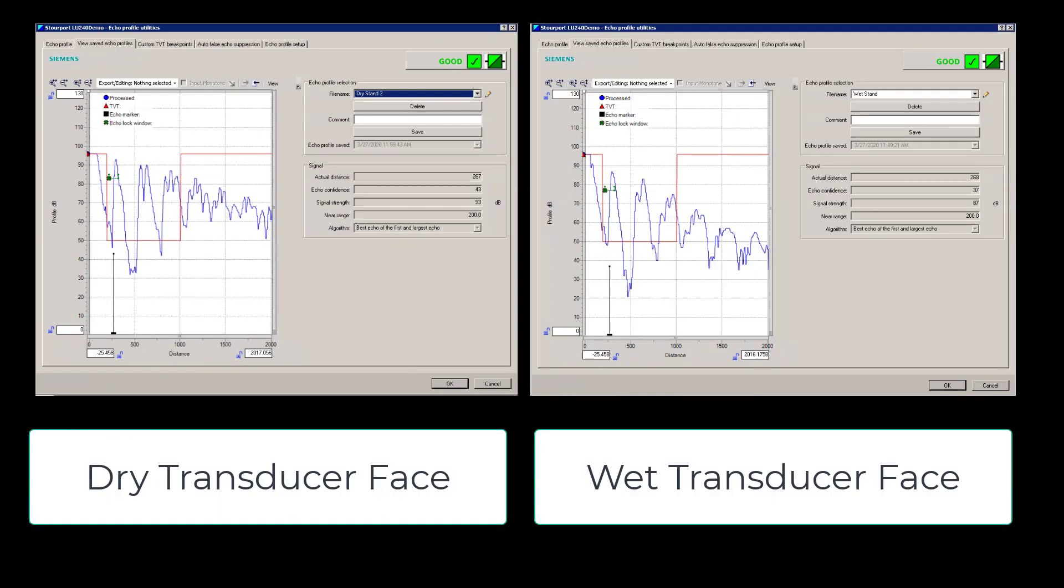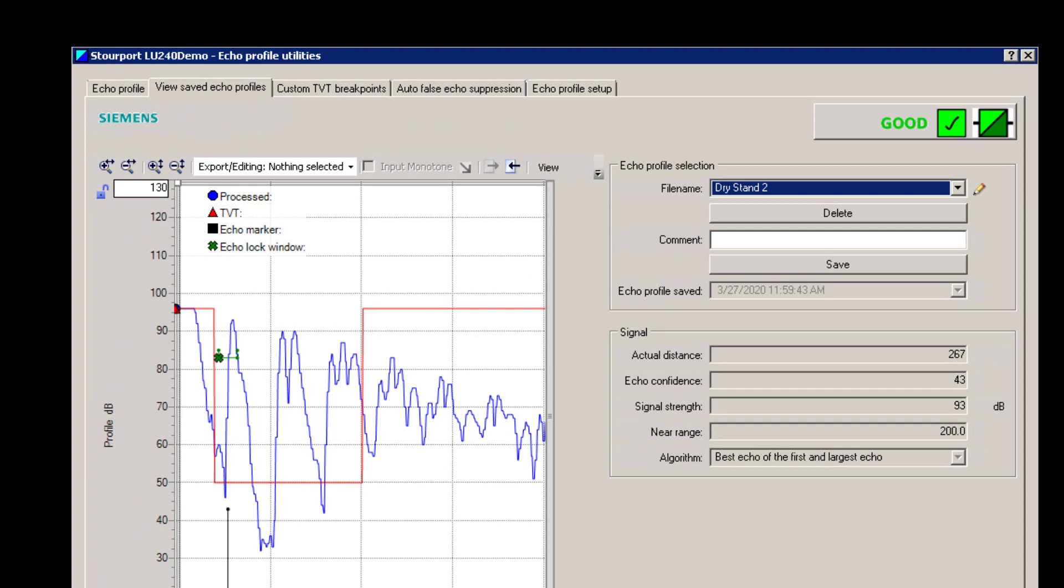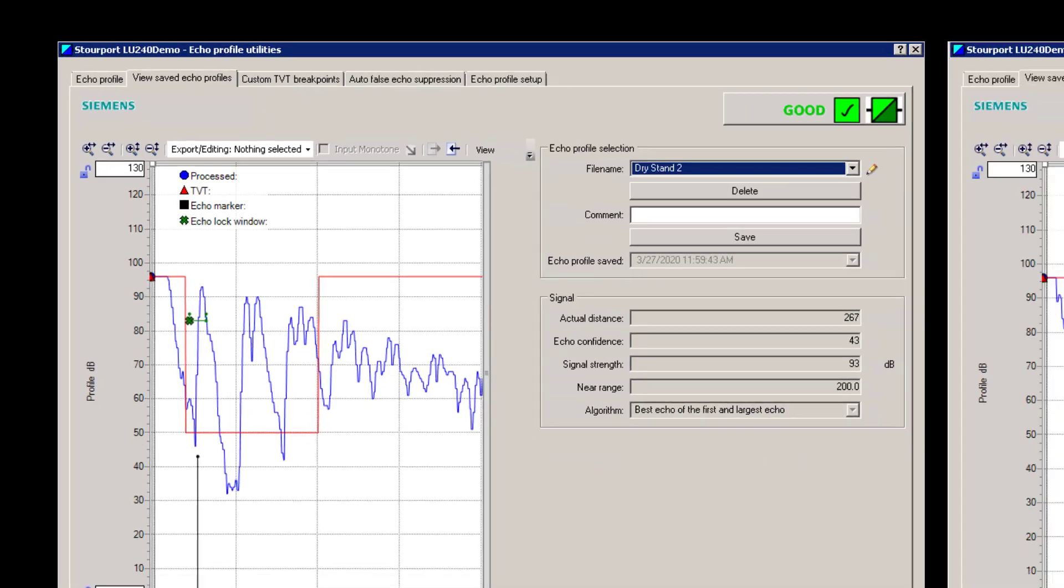You can see here we have the two echo profiles. If we zoom in on the dry echo profile first, we have a distance of 267 millimeters and an echo strength of 93 decibels.